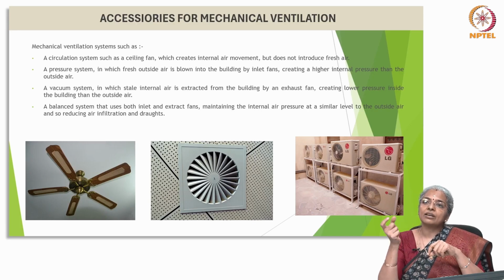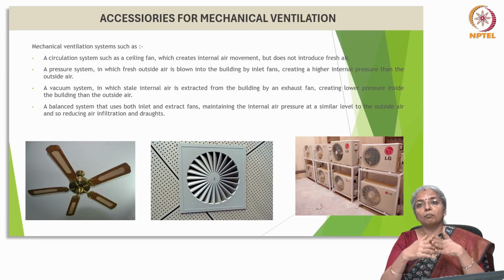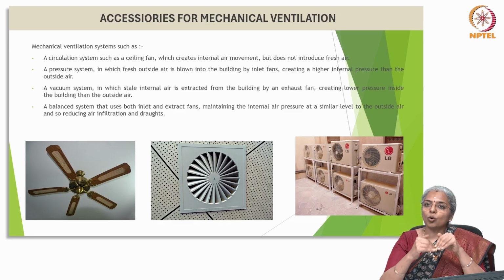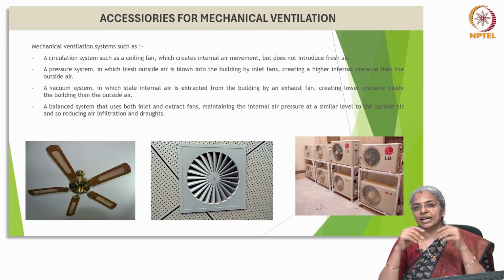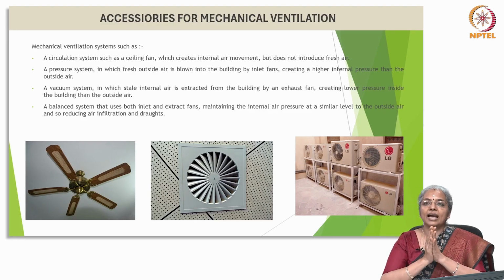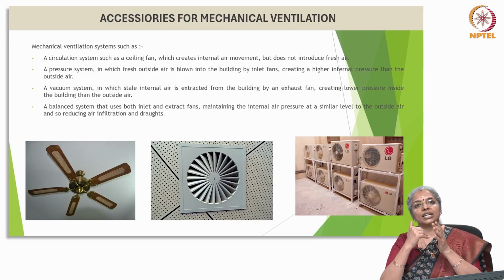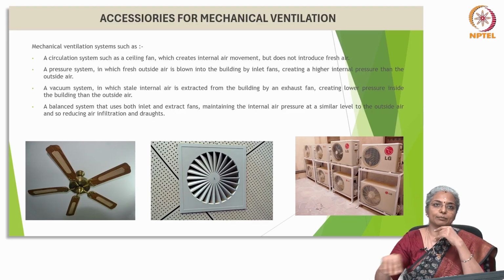A pressure system is one in which fresh outside air is blown into the building by inlet fans, creating a bigger internal pressure than the outside air. Whereas, we can have a vacuum system in which stale internal air is extracted from the building by an exhaust fan, creating lower pressure inside the building than the outside air. A balanced system that uses both inlet and extract fans, maintaining the internal air pressure at a similar level to the outside air and so reducing air infiltration and draft, is one of the best systems.